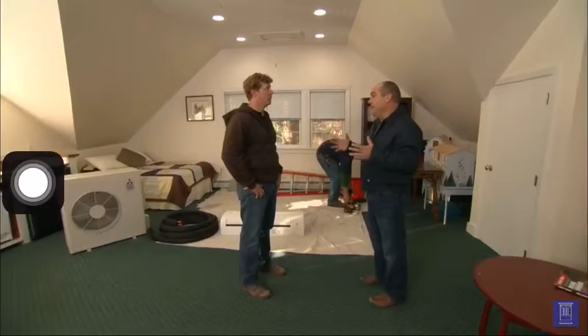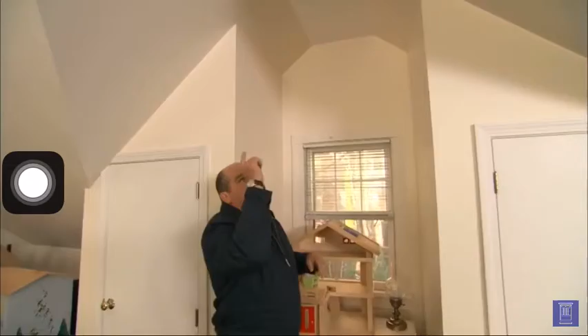Okay. So anytime I think about heating and cooling any space, it starts with a thing called the heat load. Right. How much heat is going to be lost on the coldest day to outside, and how much heat will be gained during the hottest day of the year. So we know it's 700 square feet. That goes into the calculation. Yep. What else do you take into account? Well, it's climate, the local climate, how hot or cold does it get? Yeah. Also the conditions of the walls, how much insulation is in the wall, insulation in the ceiling, in this case insulation below my feet right here, and also the level of windows.